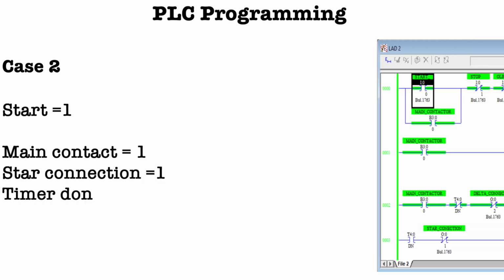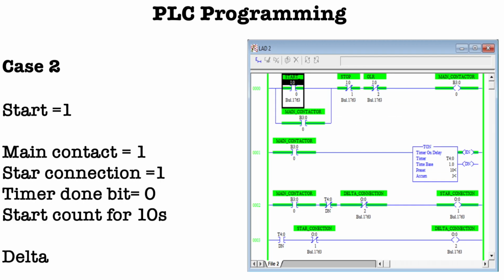Let's take the next case. When I press the start button, or when I change the state of the start switch from normally open to normally closed, you can see my main contactor gets the supply. That's why my timer is also getting the supply and it starts counting for 10 seconds. So you can see the accumulator value is changing from 0 to 10, right?